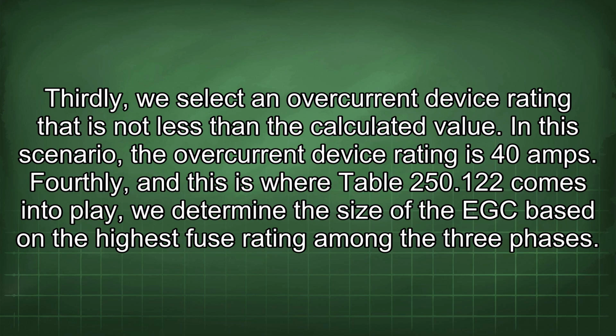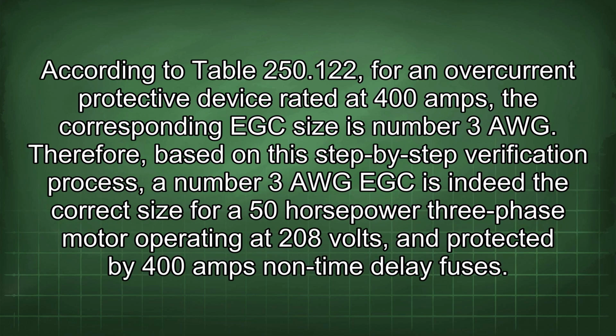Fourthly, and this is where Table 250.122 comes into play, we determine the size of the EGC based on the highest fuse rating among the three phases. According to Table 250.122, for an overcurrent protective device rated at 400 amps, the corresponding EGC size is number 3 AWG. Therefore, based on this step-by-step verification process, a number 3 AWG EGC is indeed the correct size for a 50 horsepower three-phase motor operating at 208 volts and protected by 400 amp non-time delay fuses.